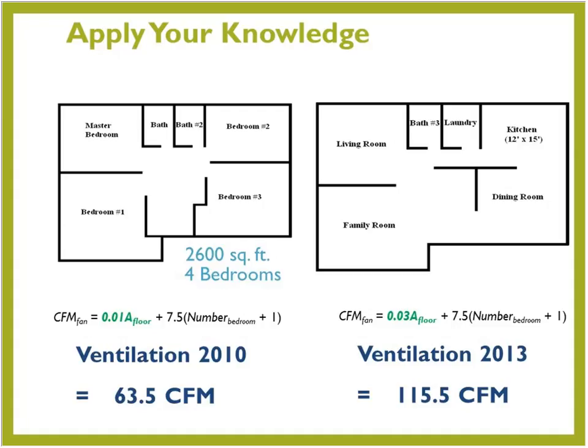This formula here that you see: number of bedrooms plus 1, because we're going to assume 2 occupants in the master bedroom, times 7.5 CFM per person, if you will. And then we also have to have a square footage calculation for the home. You'll see the difference there on the left between the 2010 calculation and the ASHRAE 2013 calculation. The only difference really is the calculation for the square footage going from 1% to a 3% calculation. And then on the bottom there, you can see the difference in the code, or the difference in the requirement of ventilation for whole house continuous using those 2 different ones.